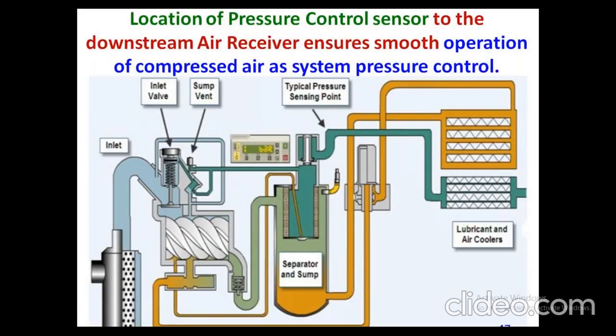We have done an energy audit in an L&T foundry. It's an ISO 50001 foundry. It's a world-class foundry at Coimbatore. We just asked the foundry maintenance person to relocate the pressure sensor. You can see on the green line, we asked them to relocate the pressure sensor from this point to the air receiver. It's a 5 KL receiver. It's a battery of compressors, 75 kilowatt, 8 numbers. After relocating this, instead of 5,500 units per day, this came to 5,000 units. 10% savings was done. Allow the pressure sensor to sense not a pulsating load, but a constant load.